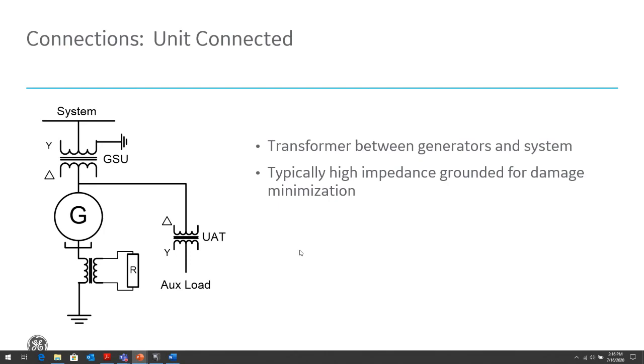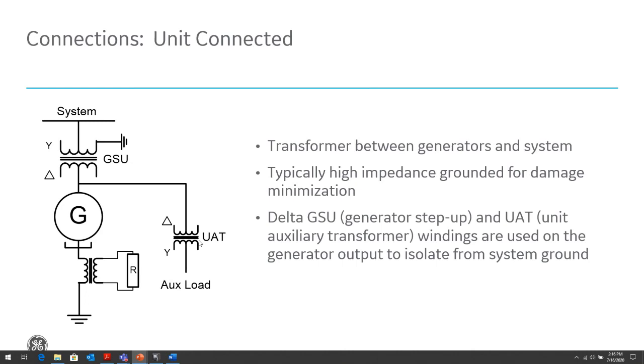The reason we do this, as I mentioned, is that these are usually large industrial or utility systems. These are fairly large generators, so much more expensive and more important to our process, generating revenue for customers or driving a large process. So we want to limit the damage caused by ground faults. And as we know, the majority of faults that happen in our power system are phase to ground faults. Again, the GSU and the auxiliary transformers are connected in delta to isolate the ungrounded generator system from the grounded system and the grounded load side.